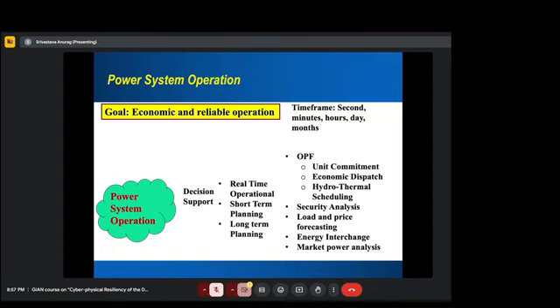So OPF, after state estimation and then power flow, we do the OPF. Why OPF? Because it has control variables, and that's why it can help with the decision support. It will give me what control to take. So the first thing we do, which is in days and hours, is unit commitment, which tells us which unit should be on and which unit should be off, so that we can match the power load with the energy generation. And the power load needs to be forecasted and known. Then we do economic dispatch in minutes, which means that once we know that this unit is on, how much power to generate using that.